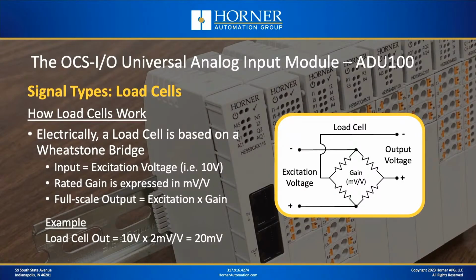Now, the way a Wheatstone bridge works is that you have something called excitation voltage, which is the input voltage for the circuit. And that might be, let's say, 10 volts. So that 10 volts of excitation will excite the circuit, and then based on the gain of the load cell, or the Wheatstone bridge, the output voltage will be generated. What is the gain? Well, the gain varies by load cell, but it's typically something on the order of, let's say, 2 millivolts per volt or 3 millivolts per volt. So the magnitude of the output of a load cell is going to be the excitation voltage times the gain. So in the case of a 10 volt excitation and a 2 millivolt per volt gain, you're going to end up with a full scale output of 20 millivolts.